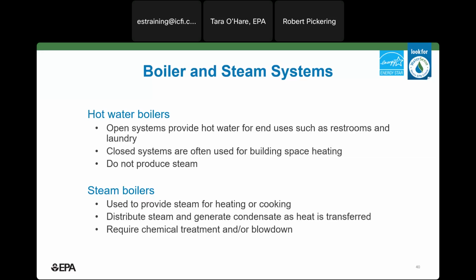Recirculating closed hot water systems for space heating, similar to the chilled water system, should have very little makeup water demand. So again, you can install a meter just to make sure that you're not losing any water in that closed loop system. But the focus for our purposes for water efficiency is on steam boilers.